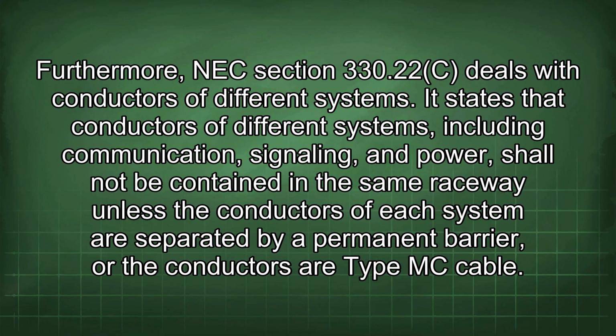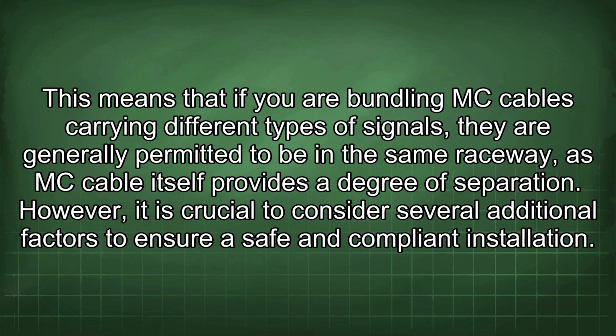It states that conductors of different systems, including communication, signaling, and power, shall not be contained in the same raceway unless the conductors of each system are separated by a permanent barrier, or the conductors are type MC cable. This means that if you are bundling MC cables carrying different types of signals, they are generally permitted to be in the same raceway, as the MC cable itself provides a degree of separation. However, it is crucial to consider several additional factors to ensure a safe and compliant installation.